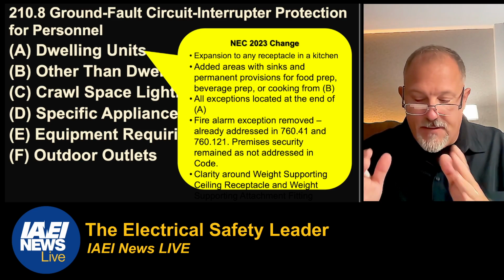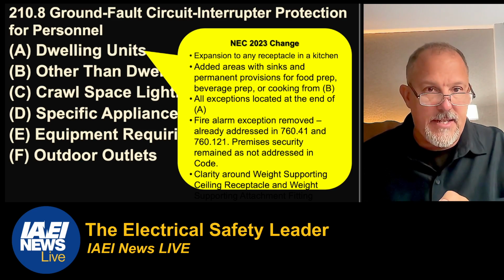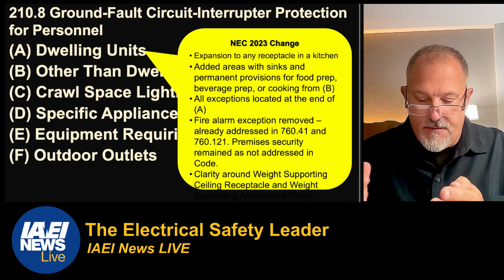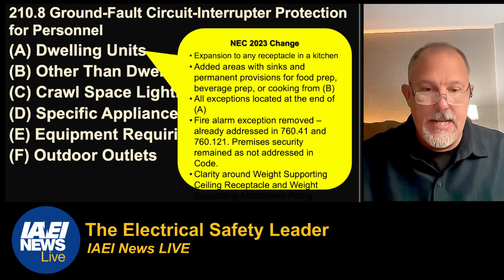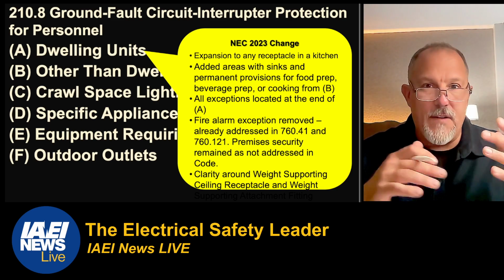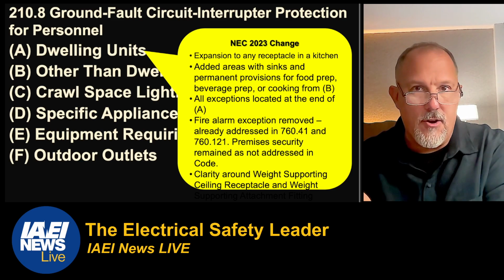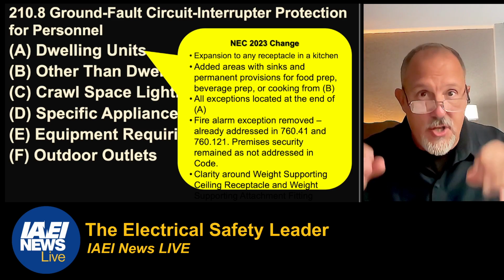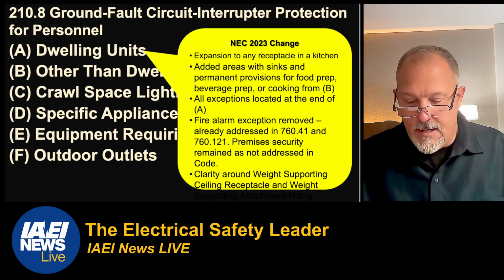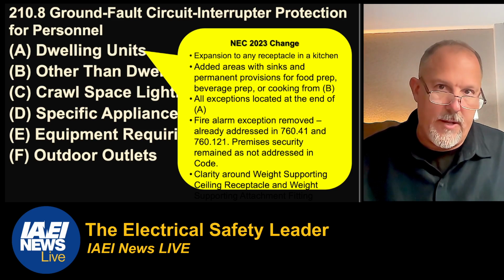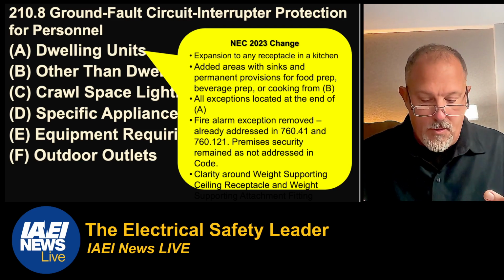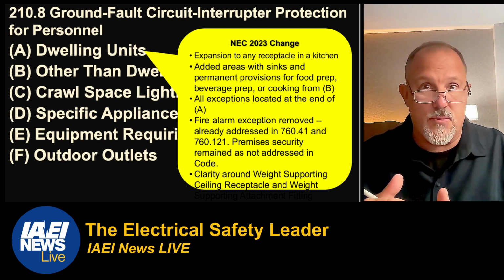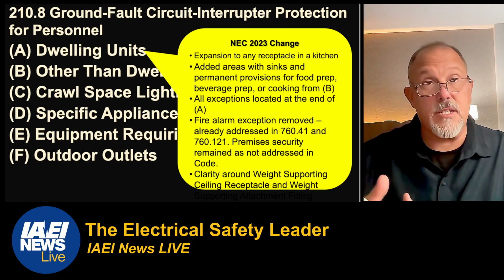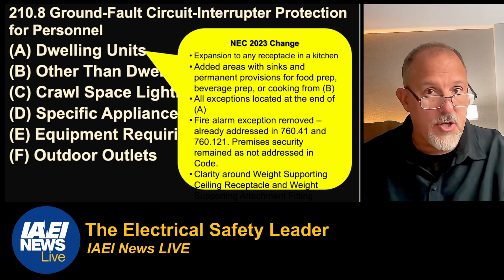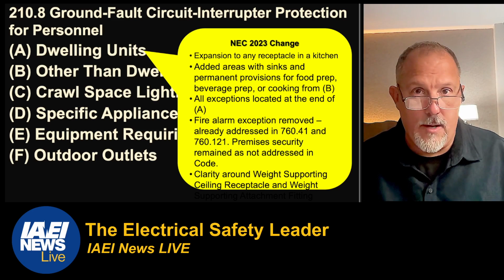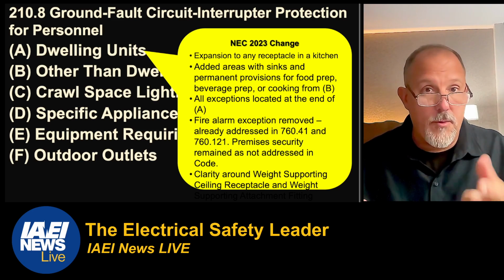So here's what we did. Fire alarms were already covered, so we removed that. In 760.41 and 760.121, fire alarms are already addressed. So we didn't have to put the exception in 210.8(A) for fire alarms because it's already in 760. If you have a fire alarm, you're not allowed to put it on a GFCI. So we took that reference out. But there's nothing in the National Electrical Code that dealt with what the code has historically called burglar alarms, but we call that premises security system. That aligns with other codes and standards. So the premises security system is not currently addressed in the National Electrical Code. I can't go to an equivalent 760.41 or 760.121 and find that you can't put those on a GFCI. So we left that in, but we removed the fire alarm.